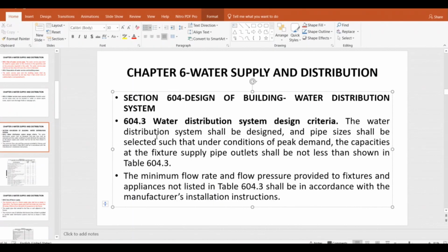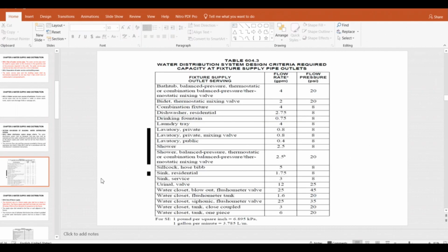But when we go for the plumbing design, normally we consider the overall fixtures, and the plumbing standard has the rule that even though you consider all the fixtures, the full water flow will not be taken. So we will see in the next class how the water flow is reduced. So the minimum flow rate and pressure are given here. When you go for the booster pump head calculation, you have to consider the last fixture with this arrangement.